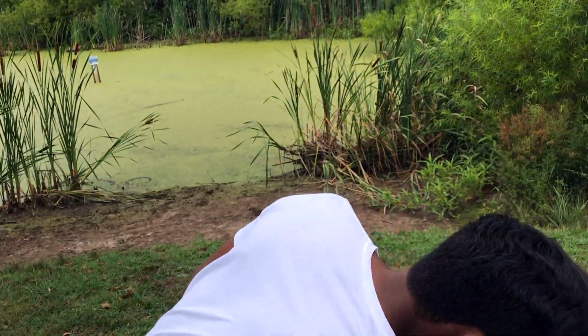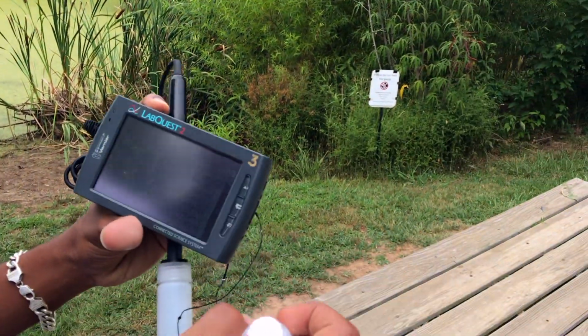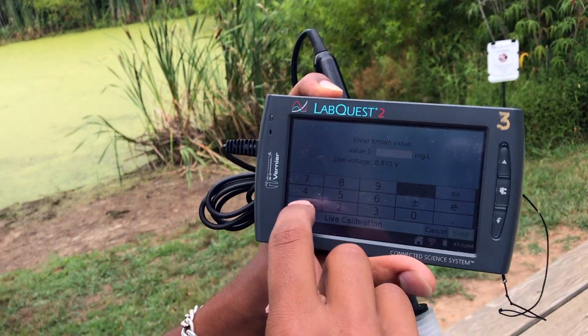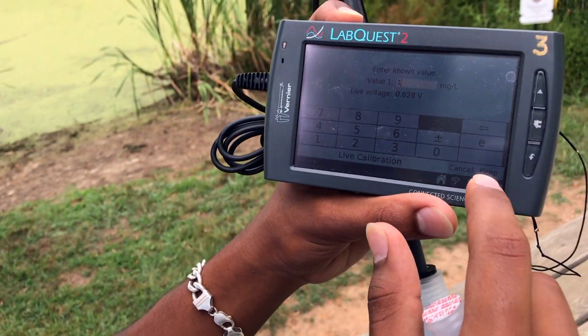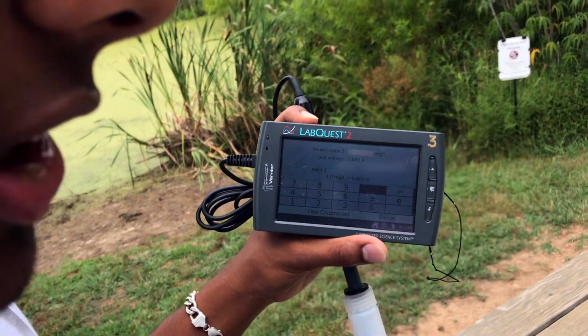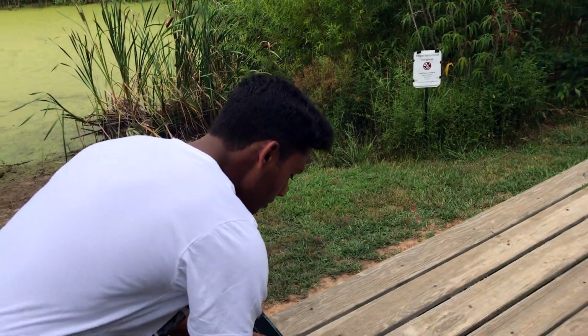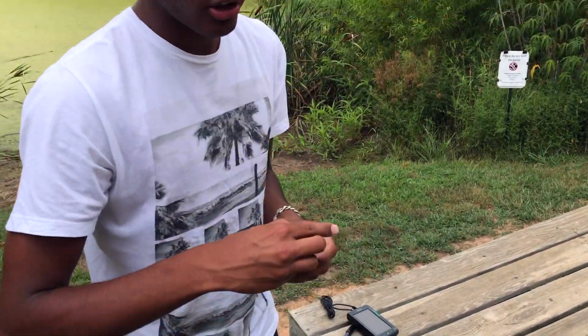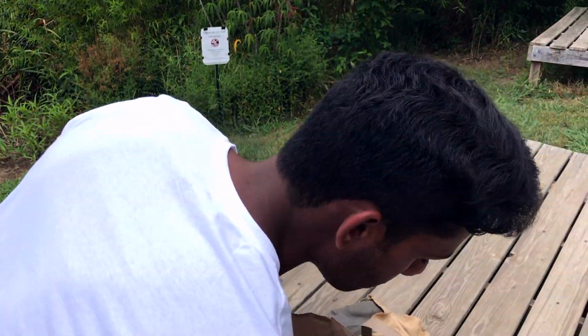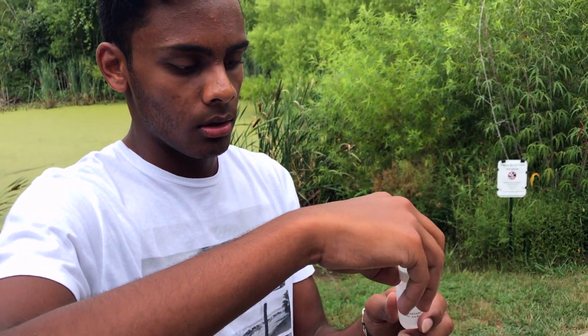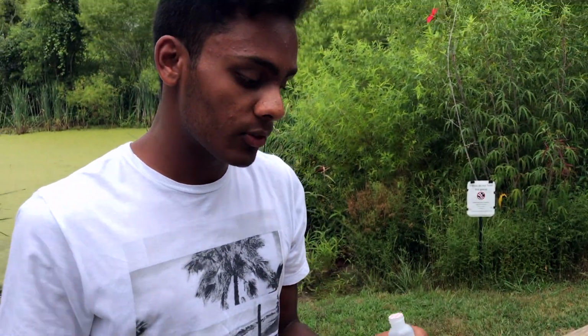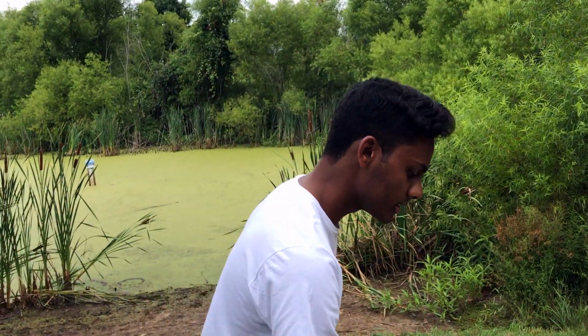You're gonna drop in the number 1 milligram per liter. So you'd go ahead, put 1, keep. And then for your next known value, again, these are new and these are expensive, so just for this demonstration purpose, I don't want to open the seal. These do have a seal for protection, and if it is broken, please be careful about what you're using, because we don't want to have wrong data.